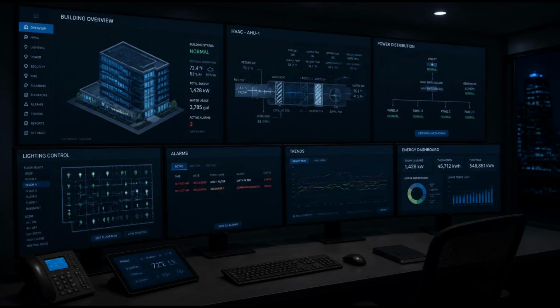Night setback is not the same as shutting off the HVAC system entirely. The system continues to operate. Air continues to circulate. The pressure balance is still maintained. Fresh air is still introduced in modest quantities to keep the indoor environment from becoming completely stagnant. What changes is the intensity and scale of the system's operation.